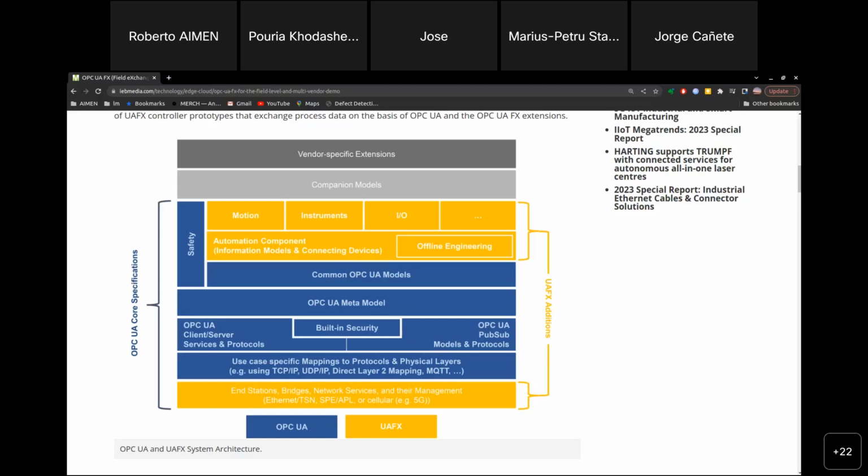And some additional ones are included with OPC UA FX. That's why I'm saying that pub/sub and FX are not exactly the same thing. So there are a little bit of additions. From the OPC UA application layer, you can ask for a given quality of service. You can say that I have this kind of needs of communication, and I would like that they be satisfied. So you can require that kind of thing.